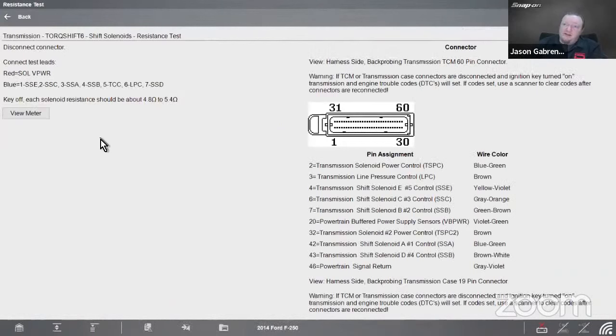Then the test we can do on this is a resistance test. So we go to solenoid power for the red channel, and the blue one goes depending on whichever solenoid we're checking. Key off, each solenoid resistance should be about 4.8 to 5.4 ohms. Outside of that range, you've got a bad solenoid.